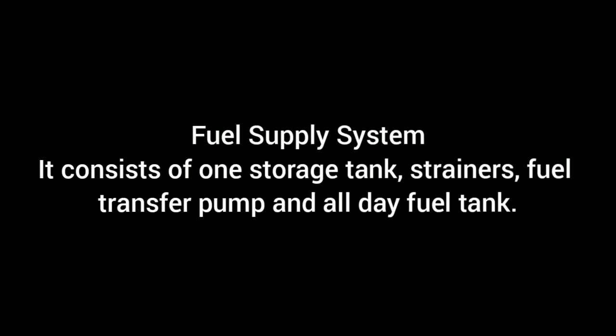Let's discuss different components of diesel power station. First one, fuel supply system. The fuel supply system consists of one storage tank, strainers, fuel transfer pump and all-day fuel tank. Oil is stored in storage tank. The oil in storage tank is pumped to day tank using a transfer pump. A strainer is placed in between the main tank and day tank to remove solid impurities. In the case of overflowing, an overflow pipe is connected between day tank and main tank so that excess oil from day tank is returned to main tank through this overflow pipe. The oil is injected to diesel engine from day tank using fuel injection pump.